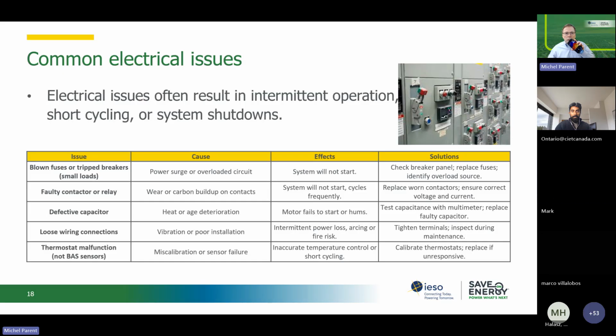If you've got a little infrared camera, so here you see I'm doing an infrared of the screen. Well, you guys probably know that if you do infrared of your electrical panels, of where your contactors are, that will provide you a quick diagnostic that you need retorquing or that you have a potential overload in a circuit. And those little infrared cameras, you don't necessarily need to call an external resource. You can provide your team with that little infrared camera, and I use it for other diagnostics that we do to try to prevent failures. It's cheap. There are multiple brands that sell similar infrared cameras, and it will allow you to identify loose wiring before they become an issue. So something to keep in mind.